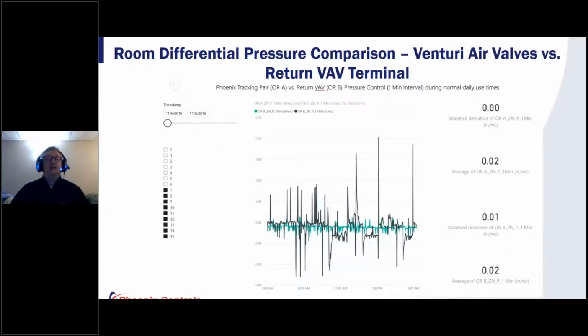Now, to prove that, here's some data to show you a pressure trace comparison between a Venturi valve and a VAV box. Now, this was done by a third party to kind of support an understanding of environmental monitoring, right, for some of these spaces. And in order to get good environmental monitoring, they needed to have stability in order to get good data from those sensors. And so they were tracing the VAV box versus the Venturi, and you can see that the spikes in the black line there are the VAV box, and the green is the Venturi valve. And again, you can see a standard deviation of less than 0.01 for the Venturi, but you're seeing spikes of over 0.02 standard deviation for the VAV box. And again, given those pressure fluctuations, that instability can compromise flow, and it can compromise some of the sensor data that they were pulling back.